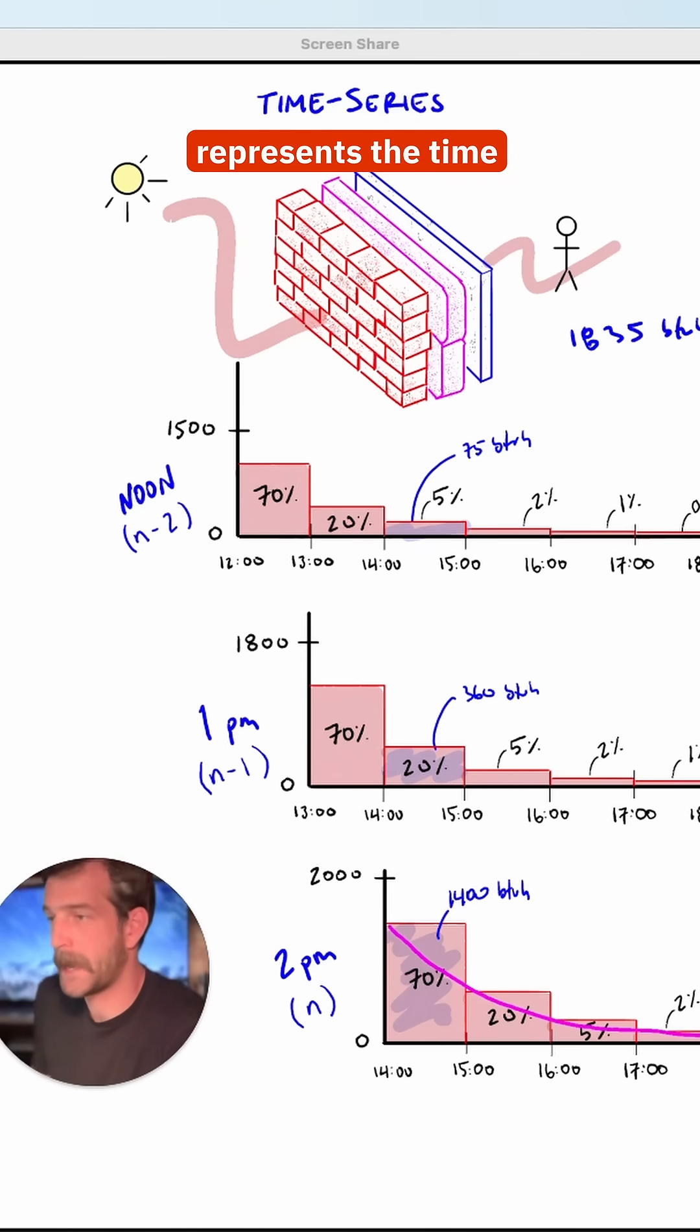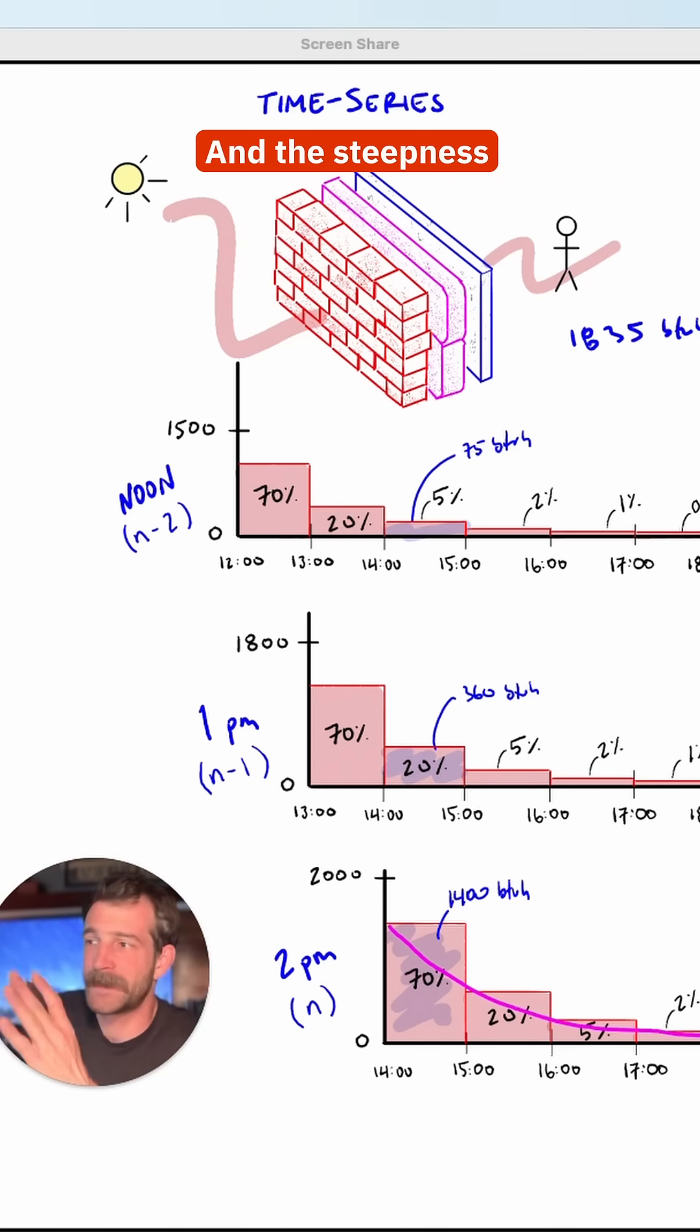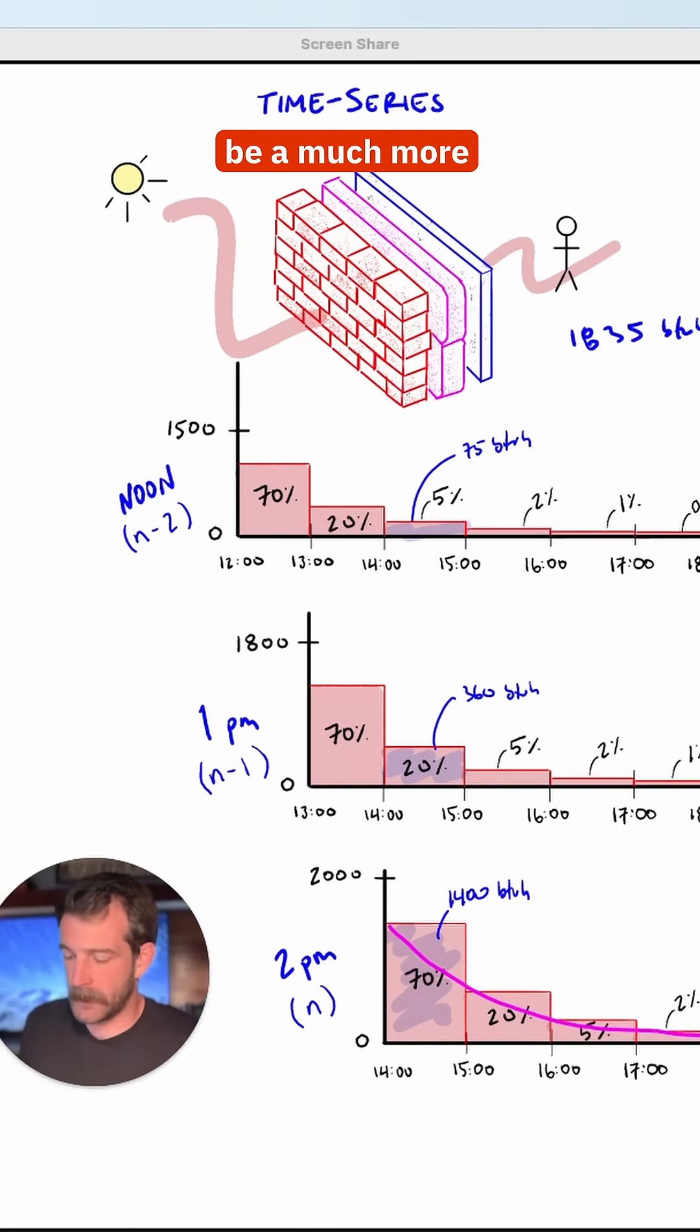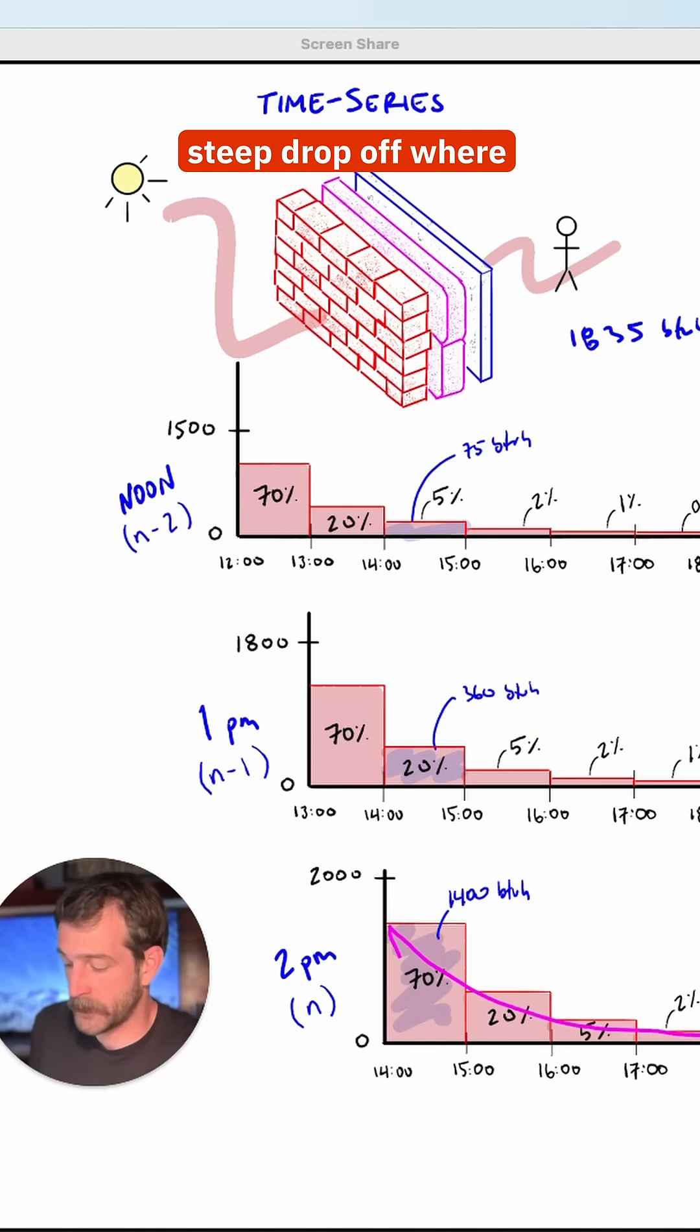This curve right here represents the time series for this assembly. And the steepness of the curve varies based on the thermal mass of the assembly. So for a high mass concrete wall, this is going to be a much more gradual curve like so. But for a window, this is going to be a very steep drop-off where most of your load will get through in the first hour and very little transfers later.